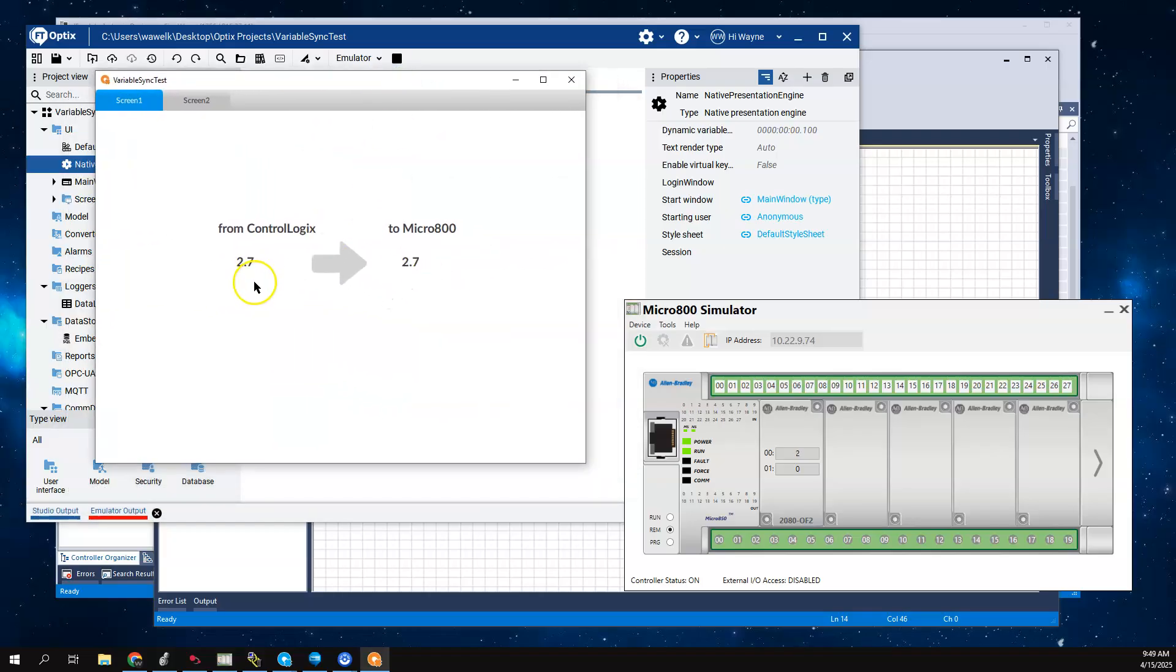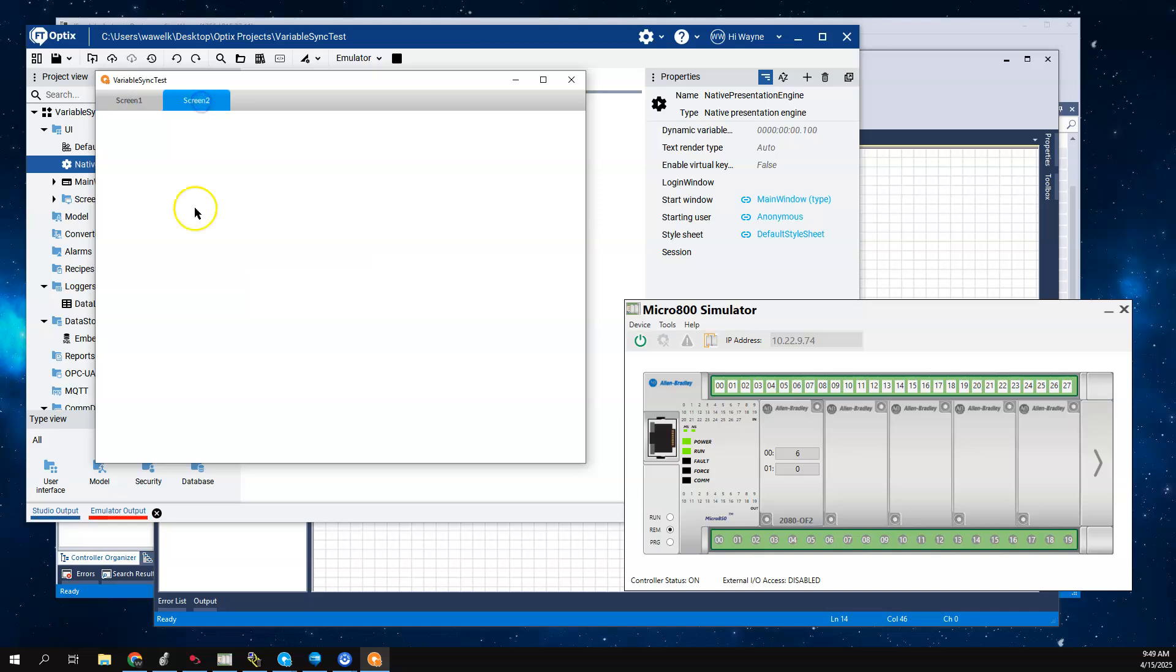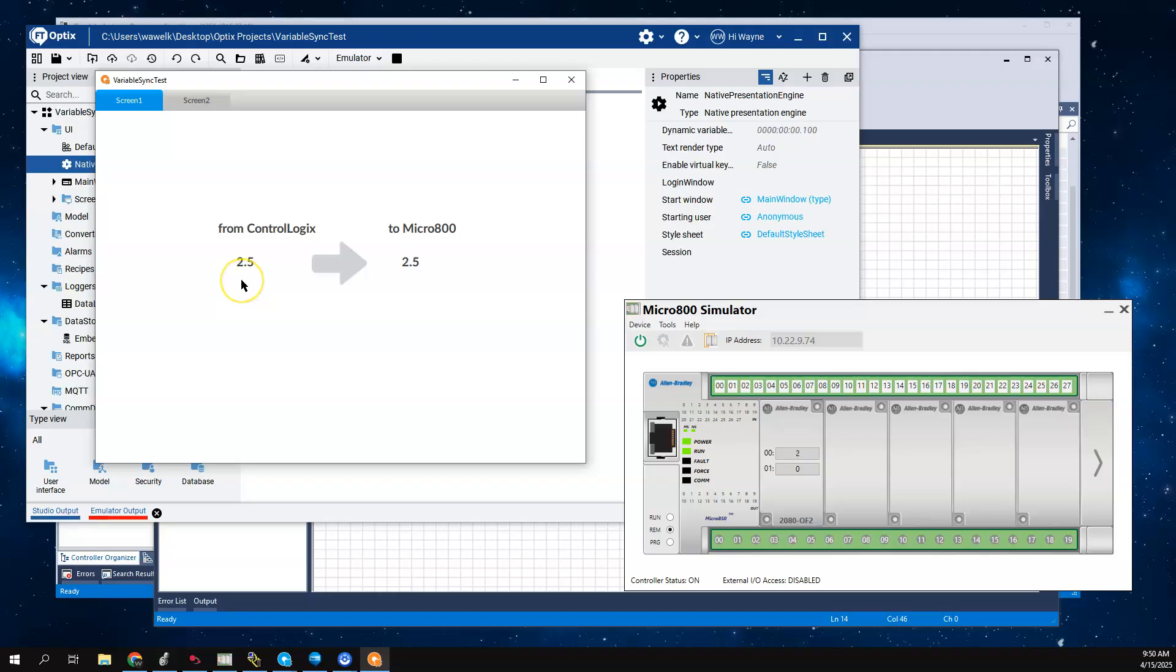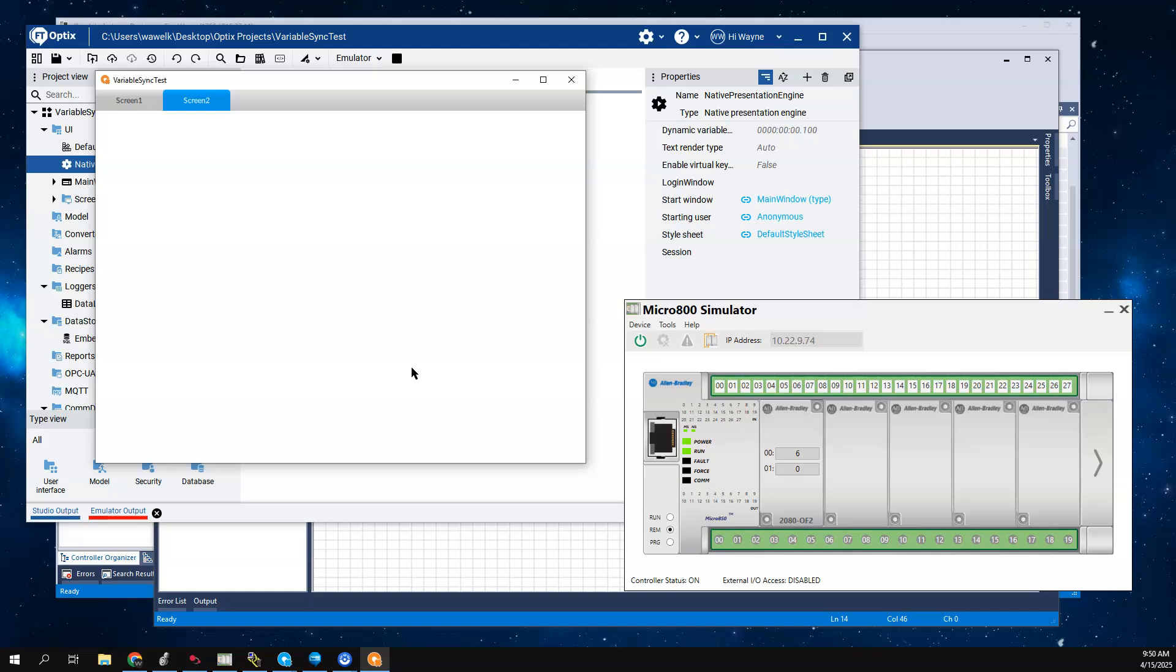Right now we're tags on scan, things are updating. If I were to switch the screen, you're going to see that it is continuing to update to the Micro 800, but at a much slower rate. That is because it's being logged at once per second, whereas here we were updating our tags at a hundred milliseconds. So if I'm logging a value, then it will be getting updated even if it's working as a headless device and it'll pass the values on to the other comm station.